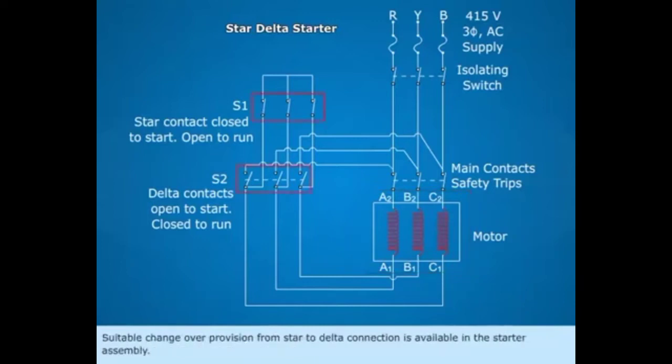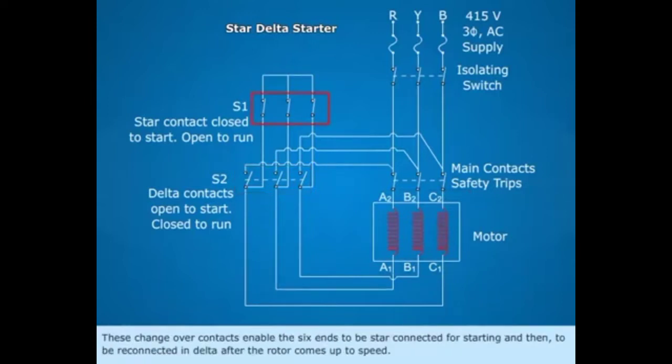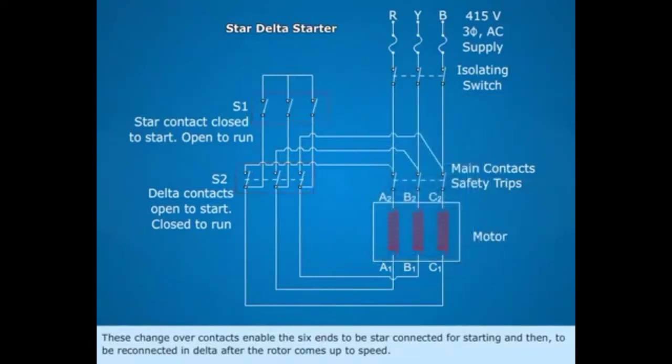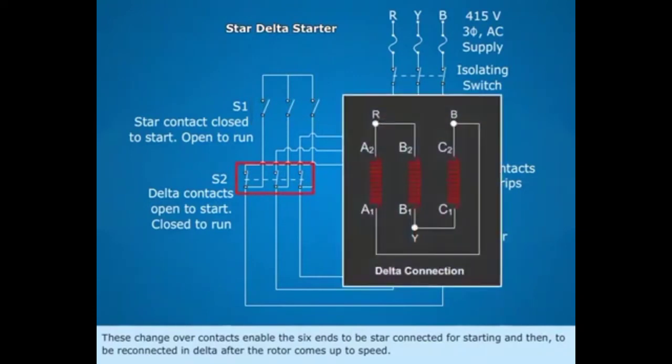Suitable changeover provision from star to delta connection is available in the starter assembly. These changeover contacts enable the six ends to be star connected for starting and then to be reconnected in delta after the rotor comes up to speed.